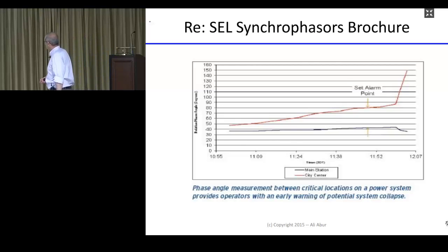So even if it's faster, let's assume that it happens within a few minutes, 3 minutes or 5 minutes. If you have a regular state estimator which runs every 2-3 minutes, you may run into a case where you may miss this because it's too slow. Even though this is fairly slow, the scan rate of the state estimator may not be sufficient for this.